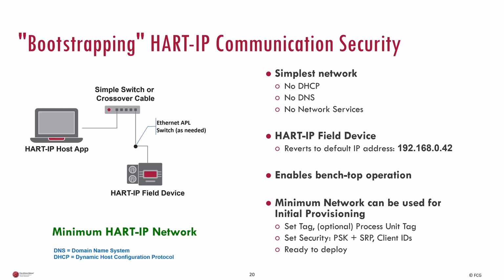So for that initial provisioning, you set the tag, you set the process unit tag if you need, you enter the user credentials, the PSK and SRPs, and now you're ready to deploy. And you've bootstrapped yourself up in a very secure way.